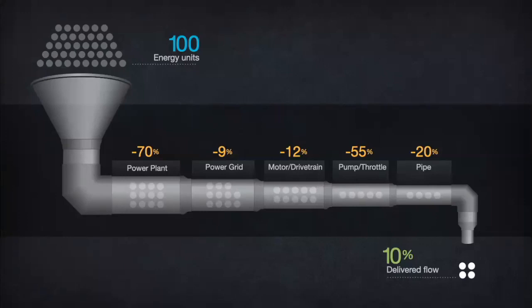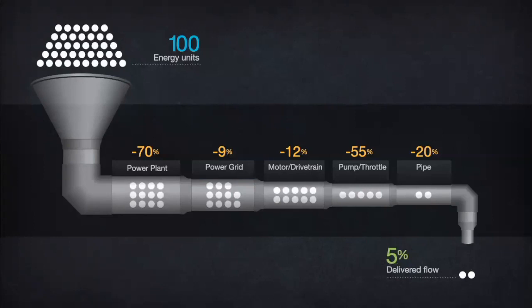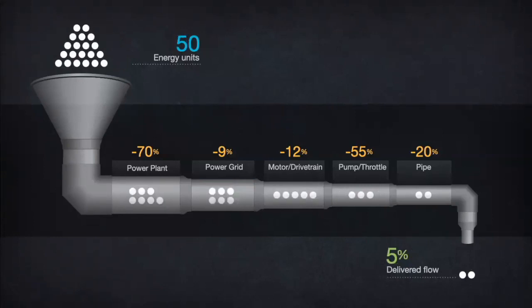But now turn those compounding losses around backwards from right to left, they become compounding savings. Every unit of flow or friction you save in the pipe saves 10 units of fuel cost, emissions, and global weirding at the power plant. And as you go back upstream, the components get smaller and cheaper, reducing the total capital cost. So always start your savings downstream.